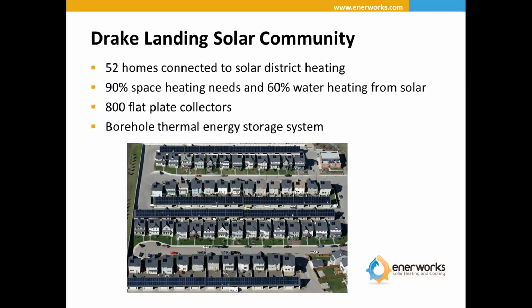So they collect that energy, and up in the top right corner of the picture, the borehole system, the building is here. So they go down, I think it's about 150 feet into the ground, and they're actually charging the earth with the heat from the solar collectors over the summer months. And then in the winter, they pull that heat out, and they won an award about 3 years ago because they were actually able to attain 100% solar heating for these 52 or 54 homes. And in addition to that, there's domestic hot water systems on each of the homes. That's a fairly unique application.